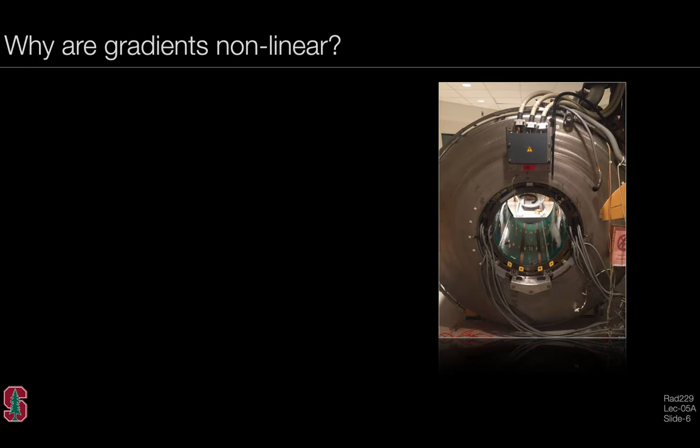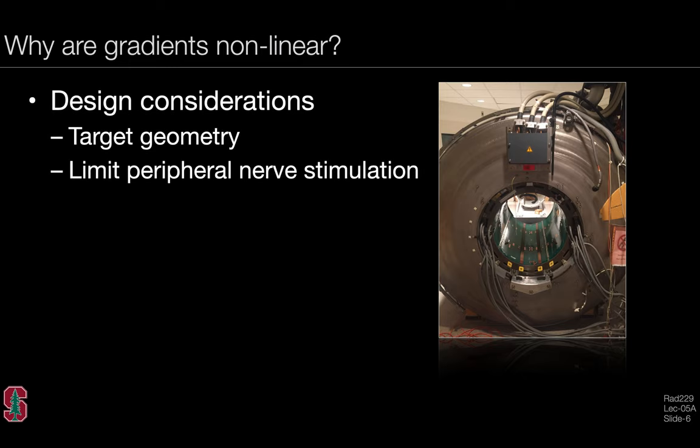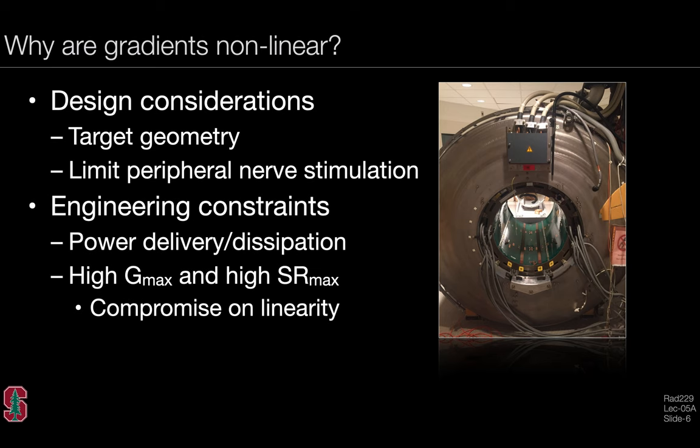So why are the gradients nonlinear in the first place? Well, to begin with, there's some design considerations including the target geometry, limiting peripheral nerve stimulation—something the FDA regulates—and engineering constraints like power delivery and dissipation. As an example, if we want really high gradient maximums and very high slew rates, something generally preferred for high sequence performance, we may have to compromise on linearity to get those gains.